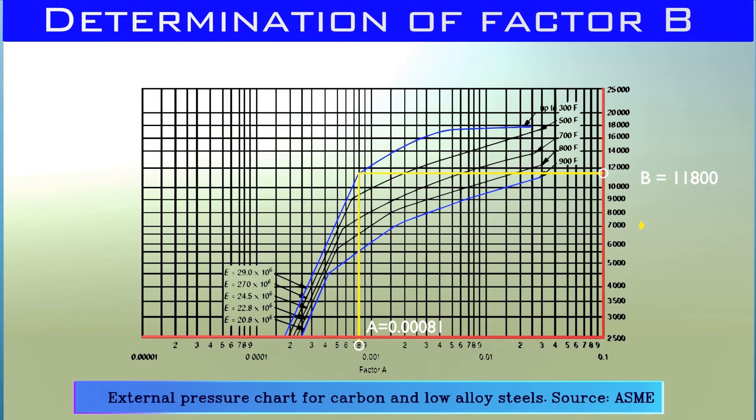Okay, but if the value of factor A falls to the left of the material lines and there is no curve in this region, then how can we find factor B? For this case, there is an equation available and we can directly find allowable pressure for this vessel. In this case, we have no need of factor A at all.